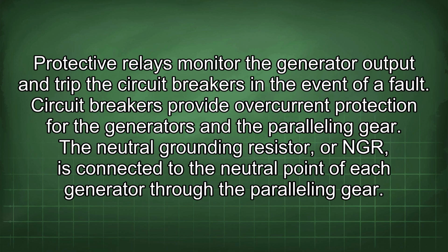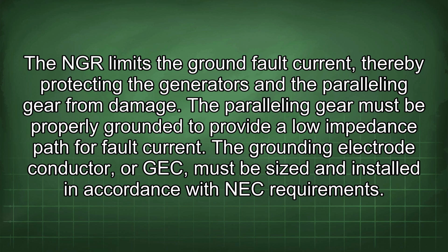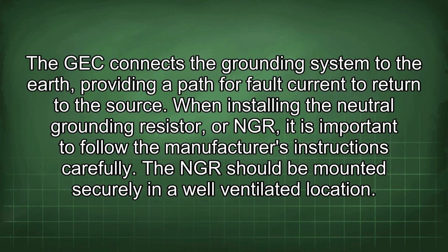The neutral grounding resistor, or NGR, is connected to the neutral point of each generator through the paralleling gear. The NGR limits the ground fault current, thereby protecting the generators and the paralleling gear from damage. The paralleling gear must be properly grounded to provide a low impedance path for fault current. The grounding electrode conductor, or GEC, must be sized and installed in accordance with NEC requirements. The GEC connects the grounding system to the earth, providing a path for fault current to return to the source.